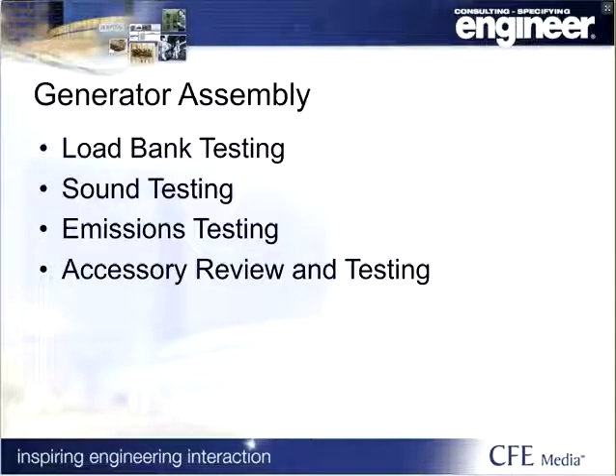The first one's pretty simple. It's the generators. Everyone is aware there's going to be a load bank test for generators. You may have sound testing. You may have emissions testing. You may have to review accessories, like, for example, the jacket water heater is actually required to go off when the generator reaches a certain temperature.